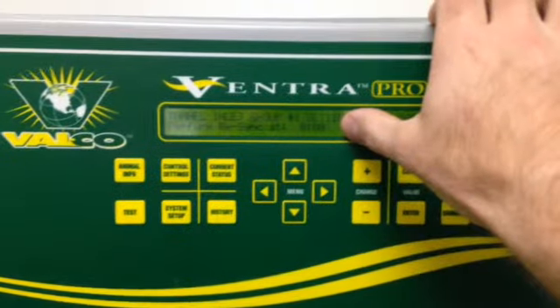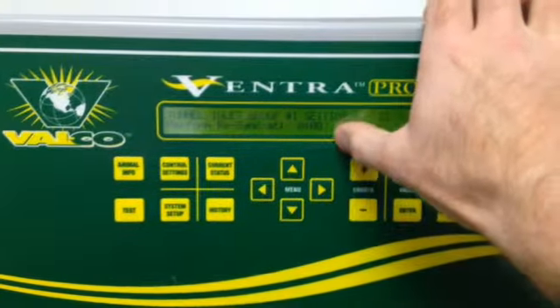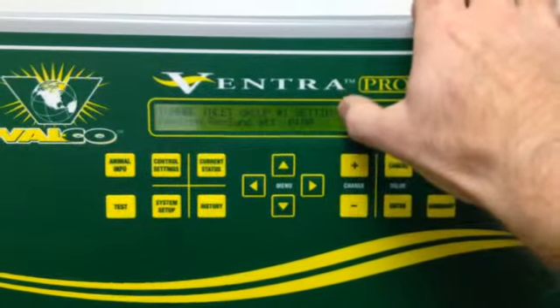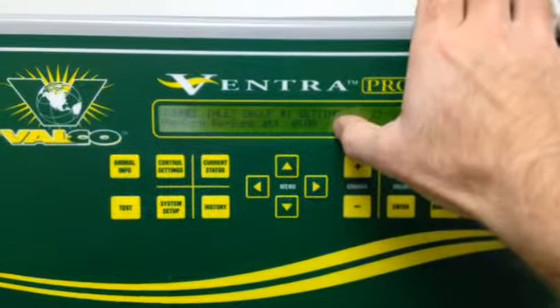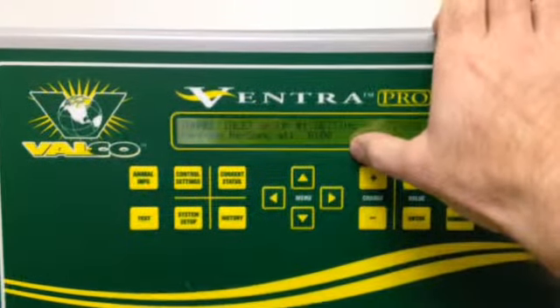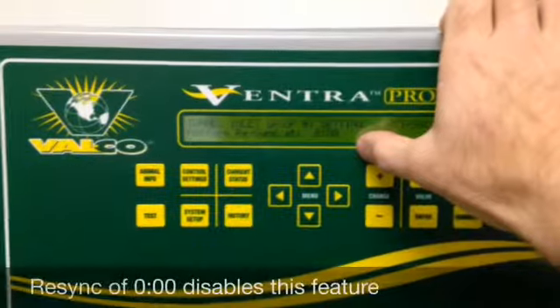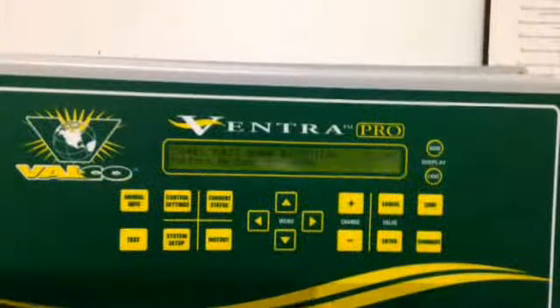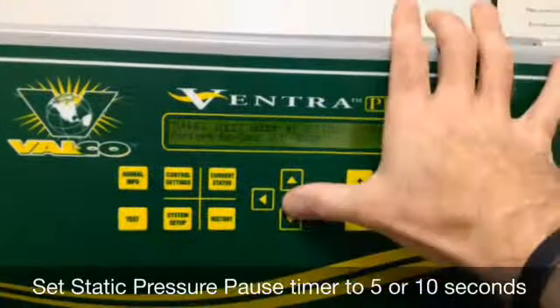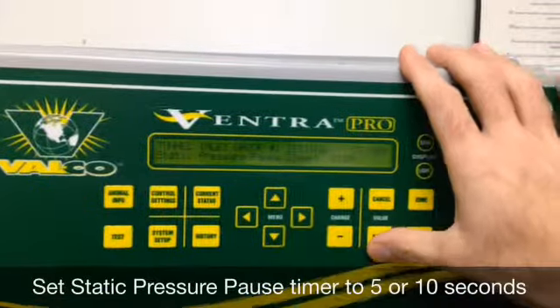Resync is simply a function to allow the controller to get back in touch with where the curtain may actually be in the absence of a potentiometer. Once a day, based on a 24-hour time clock, you can tell the controller to fully close or fully open the curtain. The last setting after the resync is static pressure pause timer.